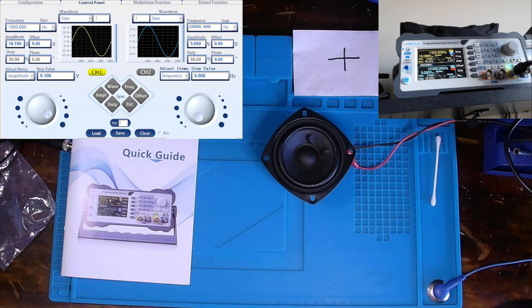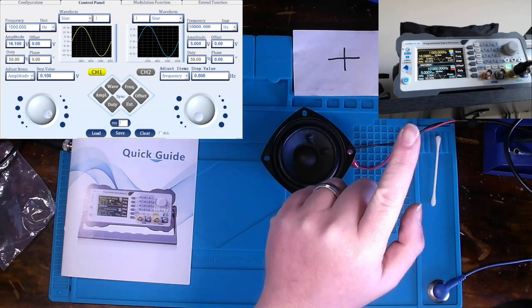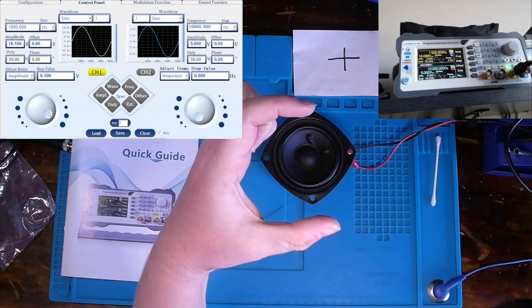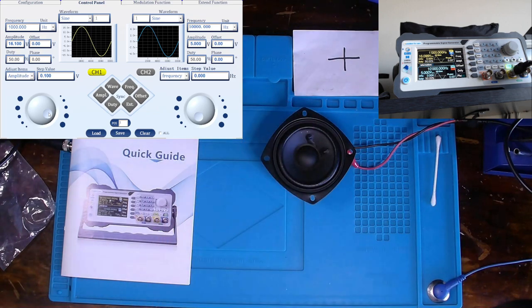As a matter of fact, you probably heard a click, and that's just, as the device is amplifying or increasing the amplitude of my sine wave here, it has to select up different amplifiers in order to do that work. And you probably just heard a click again. So we'll take this back down to roughly 2 volts.